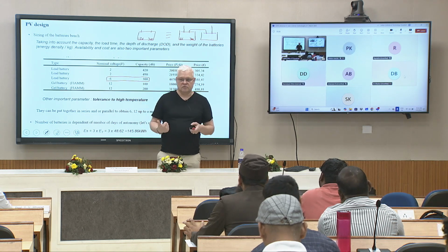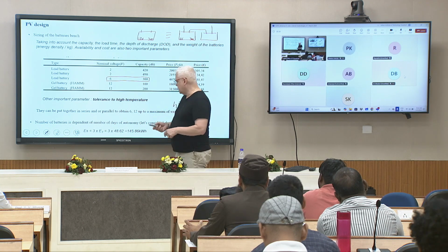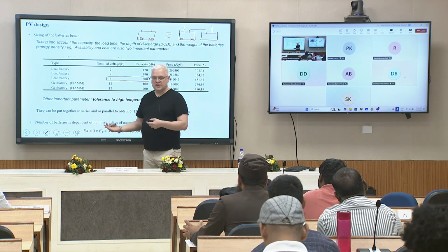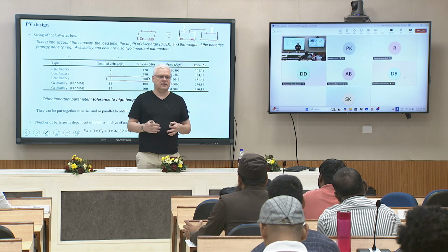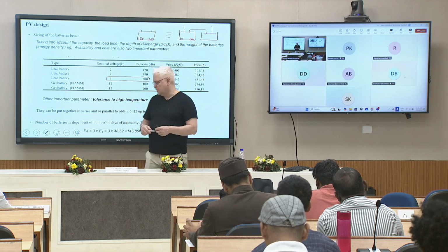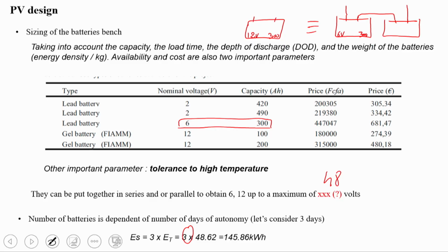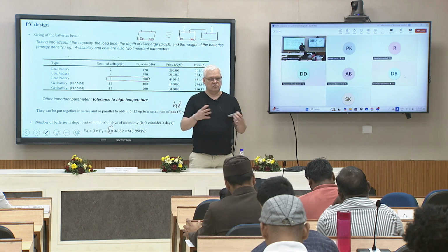So you have to investigate local data. Today we don't have the possibility, but usually when you have a battery rack, you choose around 2 or 3 days of autonomy. It could be more precise, discussing with the customer the use of the building, the period of use, and also the local climate.